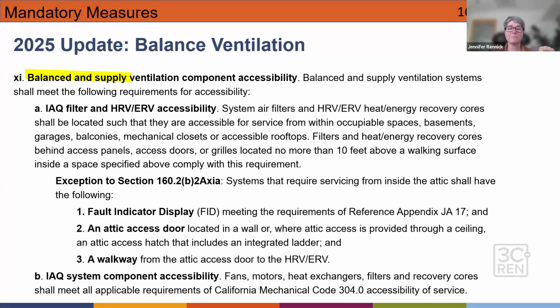And all the parts and pieces need to be accessible. So mostly we're talking about the air filters and the HRV or the ERV energy or heat recovery cores, and they need to be accessible from within the occupiable space or a basement, a garage, a balcony's okay, mechanical closets, accessible rooftops are okay. They also need to have their access panels located no more than 10 feet above a walking surface. There is an exception, and that's if you put it in an attic.